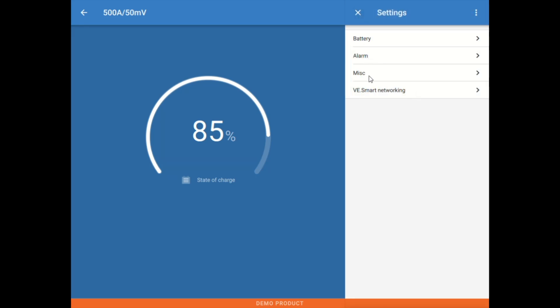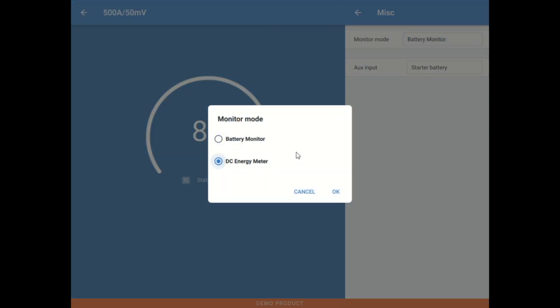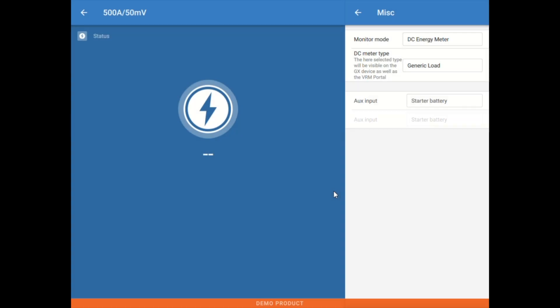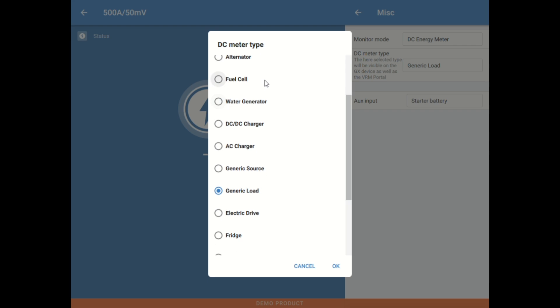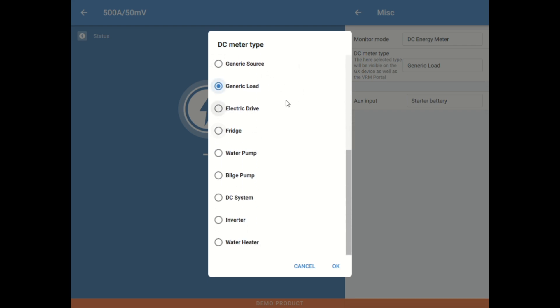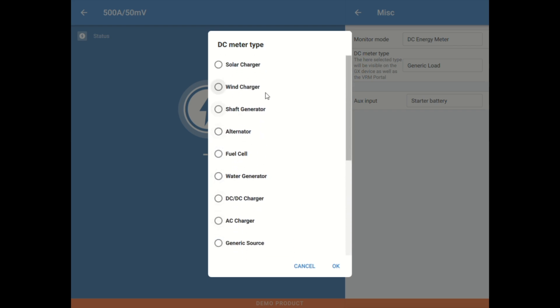Below the alarm tab, we have the miscellaneous tab. A couple of things I mentioned in here. This monitor mode, for most cases, we're going to be using this meter as a battery monitor, but these meters can also be used as DC energy meters. When we do that, we can then define what kind of energy or what the source of the energy this meter is measuring. That's particularly helpful if we want to measure other devices that are not Victron but still have some understanding of what they are. Or the system and the VRM portal will have an understanding of what those loads are, what those devices are. This is quite valuable for trying to bring in data, again, from third-party non-Victron devices.